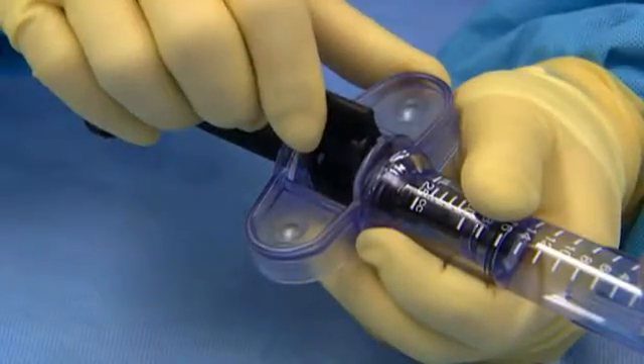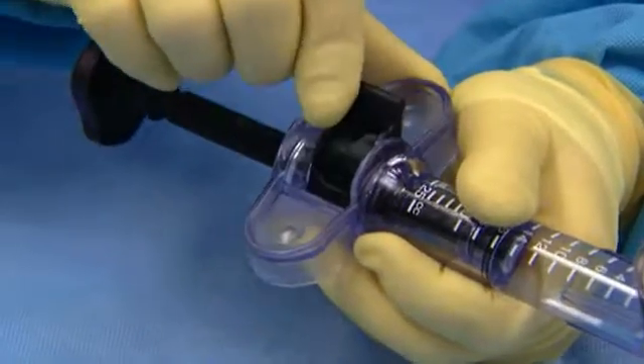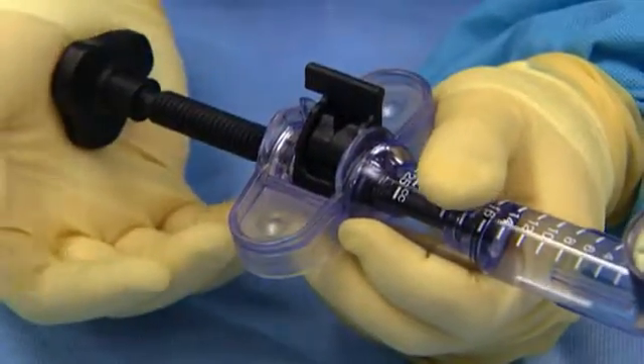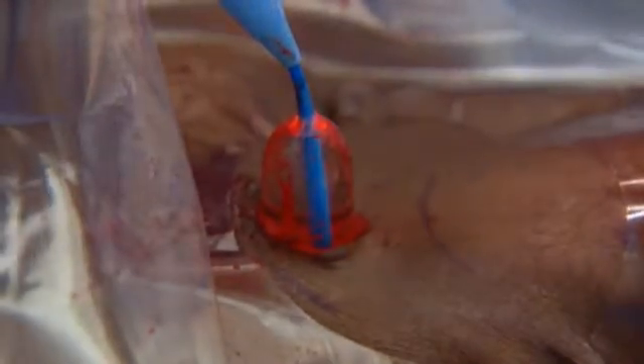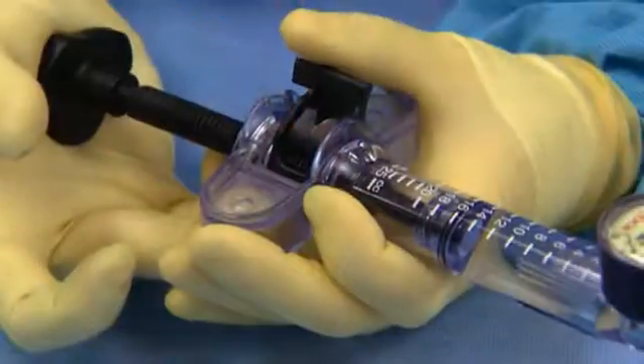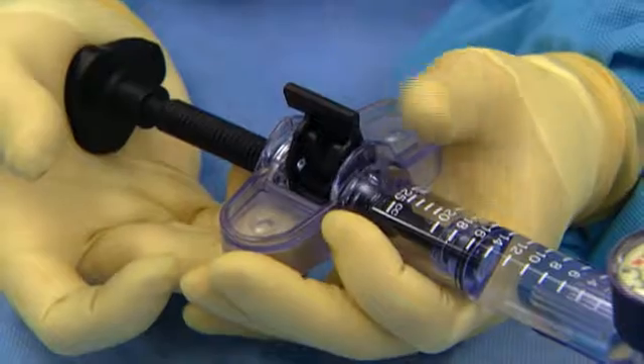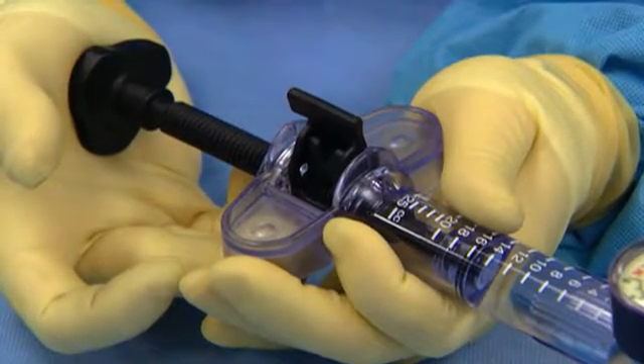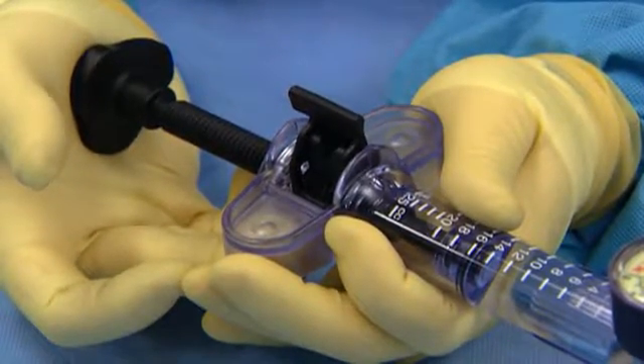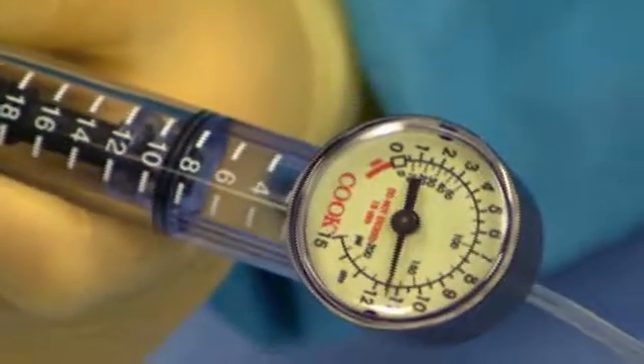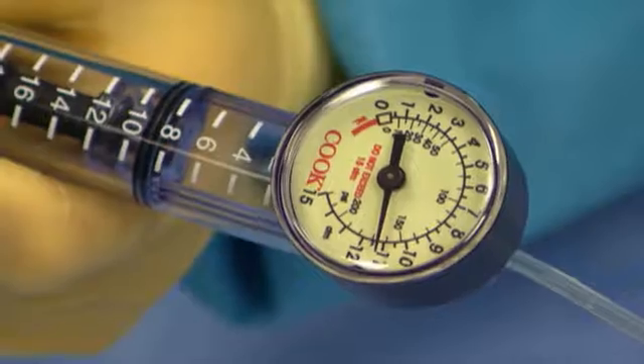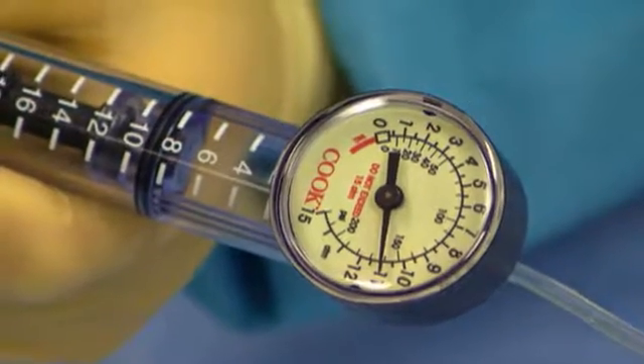The lock lever on the Cook inflation device is slid to the left to disengage it and to allow free movement of the plunger. The balloon is inflated firmly, and then the lock lever is slid back to the right to engage. This will maintain the pressure and allow higher inflation pressures to be reached. Clockwise rotation of the palm grip on the inflation device is performed until the desired maximum pressure of 11 atmospheres is reached. The inflation pressure is held for 5 to 10 seconds, which allows appropriate dilation for the tracheostomy tube passage.